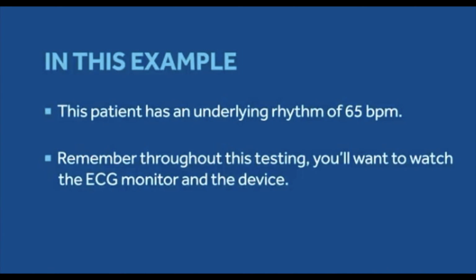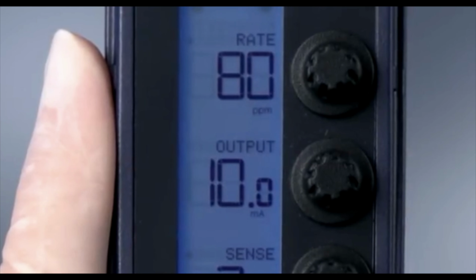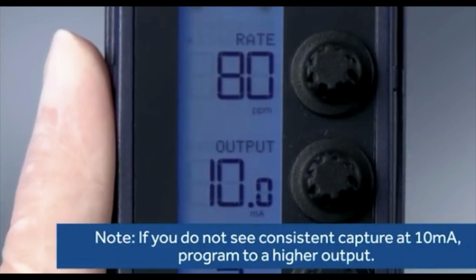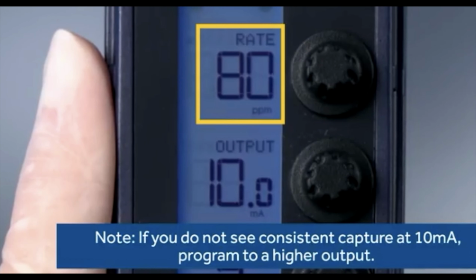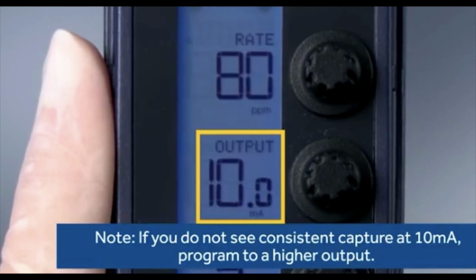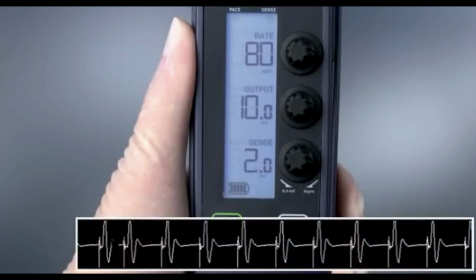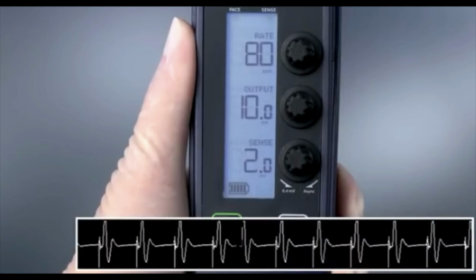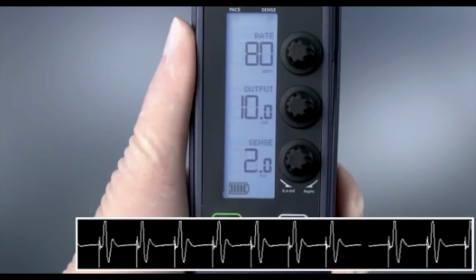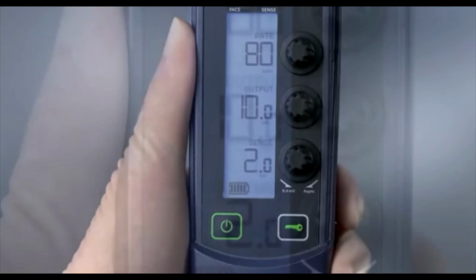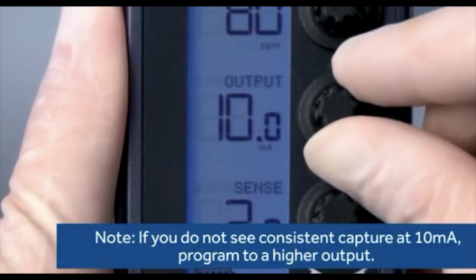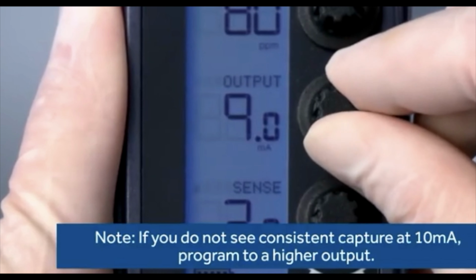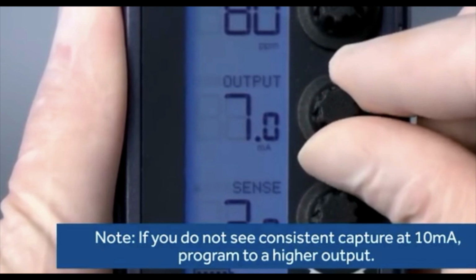This patient has an underlying rhythm. Remember, throughout this testing, you'll want to watch the ECG monitor and the device. First, increase the rate to at least 10 paces per minute above the patient's intrinsic rate. Next, turn the output to 10 milliamps. Verify that you see a rhythm consistent with pacing on the cardiac monitor, as well as the pace indicator on the device. Slowly decrease the milliamps by turning the output dial counterclockwise until the ECG shows loss of capture.